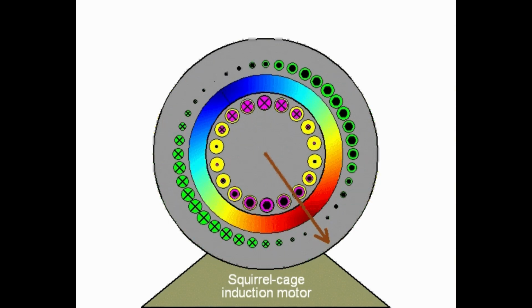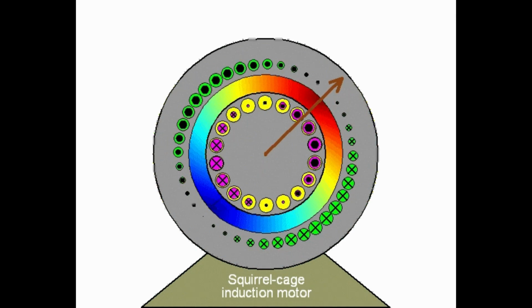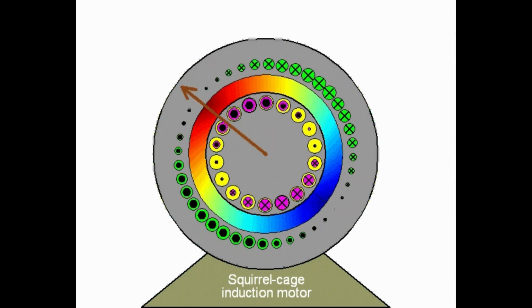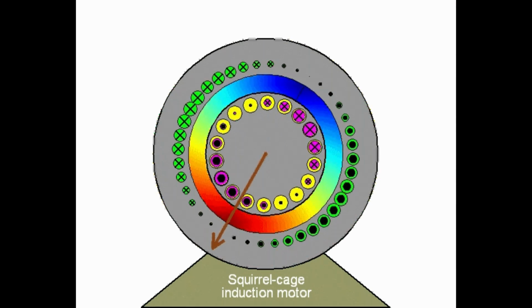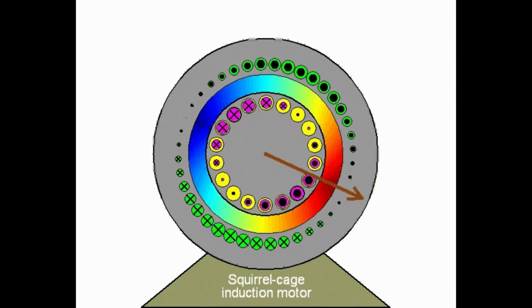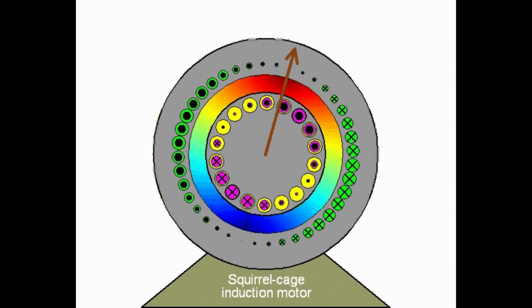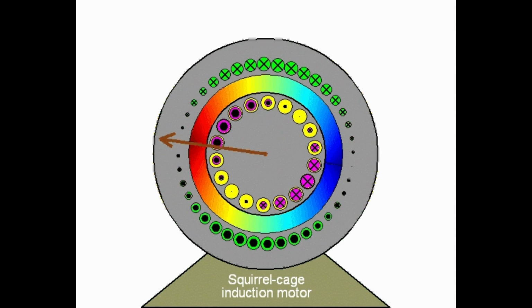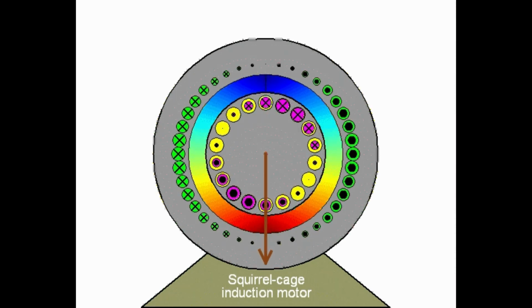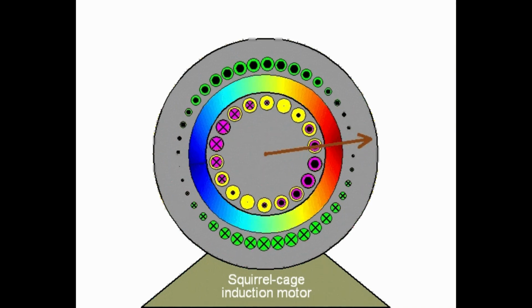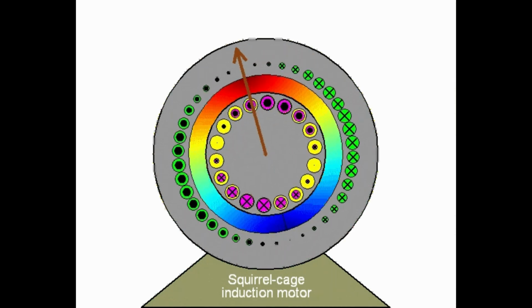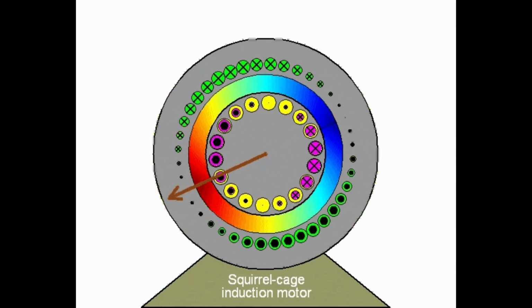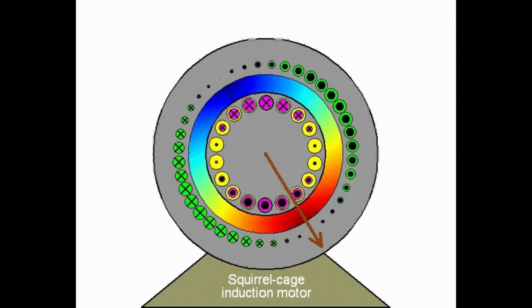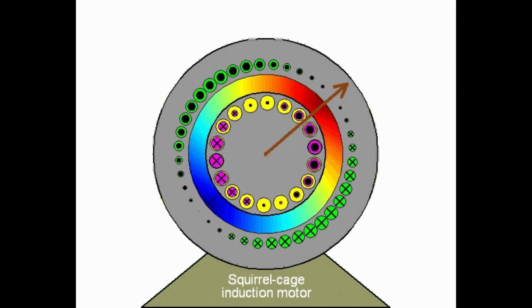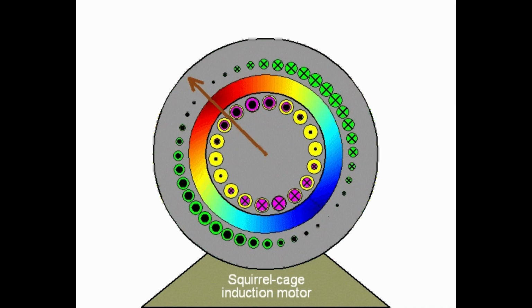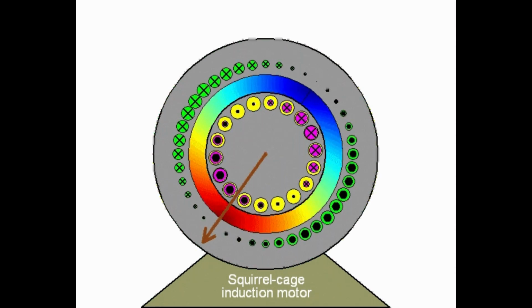Of these methods, the two most fundamental ways of starting squirrel cage motors are full voltage starting and reduced voltage starting. Once again, full voltage starting can be used where the driven load can stand the shock of starting and objectionable line disturbances are not created. Reduced voltage starting may be required if the starting torque must be applied gradually or if the starting current produces objectionable line disturbances.